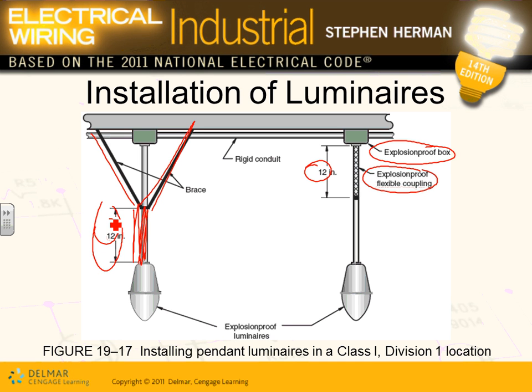So if you have a pendant, they call it a pendant luminaire, you can either have a conduit like this, but you have to support the conduit, or you can have a conduit or a cable, and you can have an explosion-proof flexible coupling to hold it. And look at the fixture. The fixtures are explosion-proof fixtures. So when you start working on aircraft hangars or gas stations or commercial garages, always pay attention to the type of fixtures and the type of equipment you install.